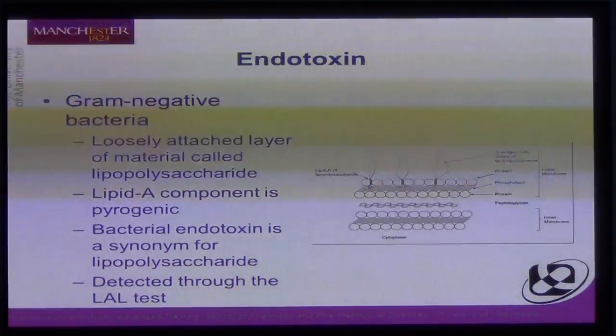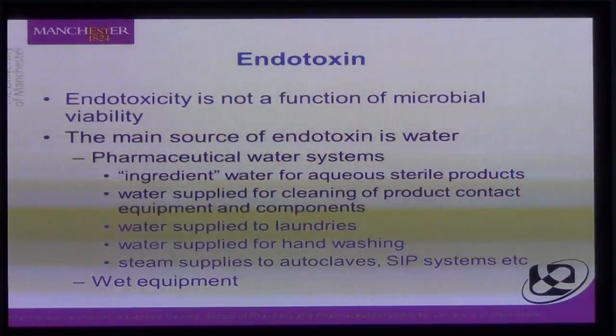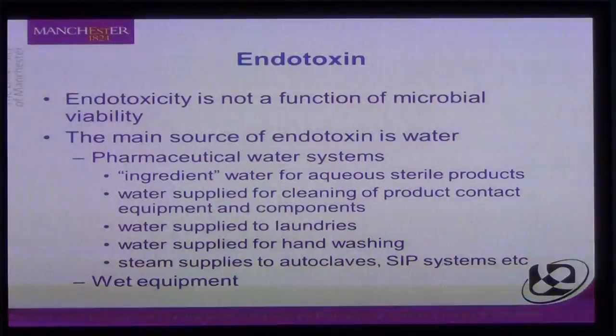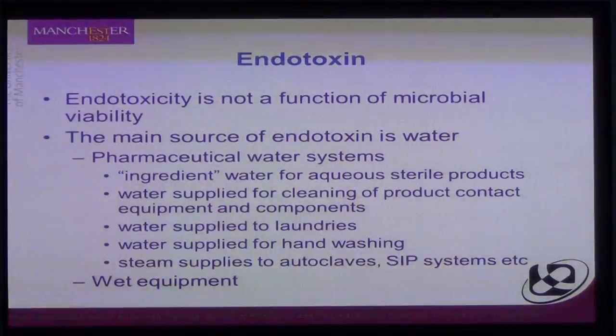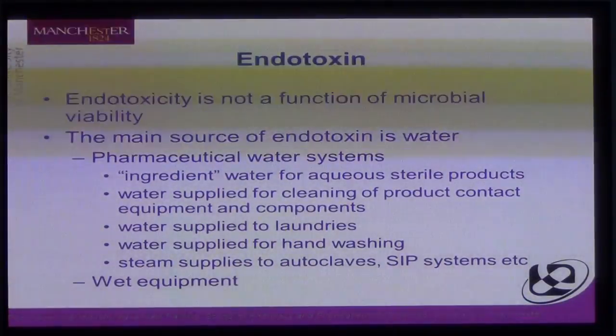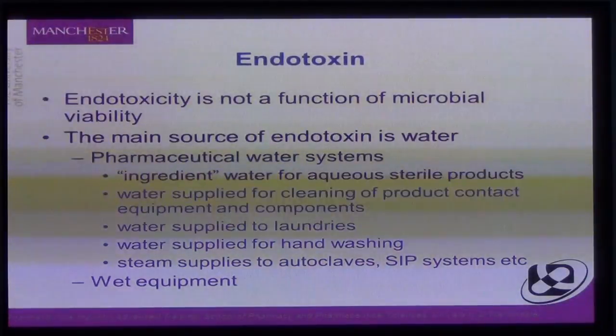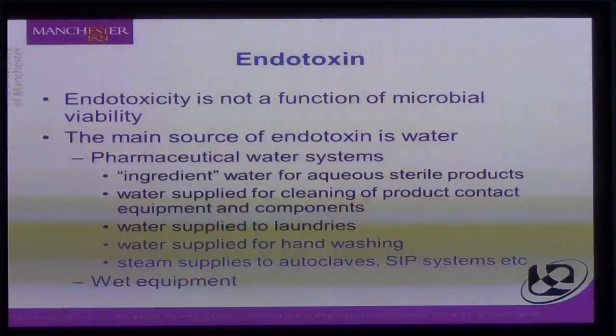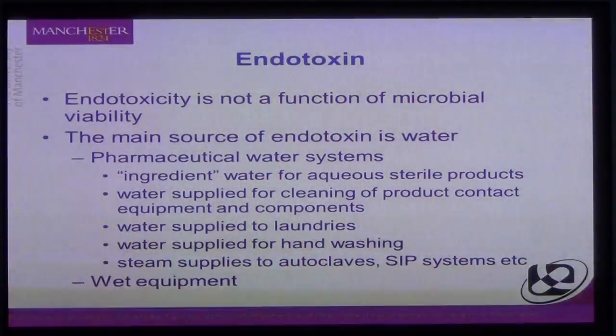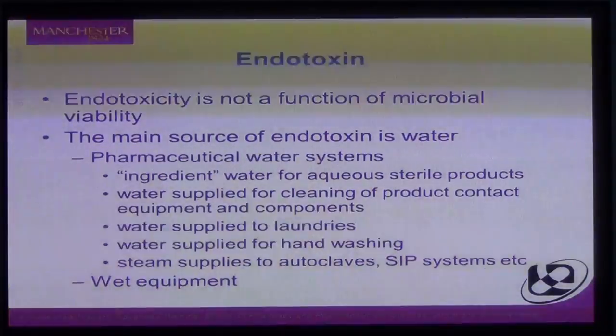It's important to recognise that endotoxicity is not related to viability — you can have a sterile solution with no viable microorganisms but still have endotoxin present. Within pharmaceutical processing, the main source of endotoxin is water. We can't get away from water since it's the main ingredient for aqueous sterile products, needed for cleaning product contact equipment and components, laundry, staff hand washing, supplying steam, and washing equipment. We just need to be better at controlling it.